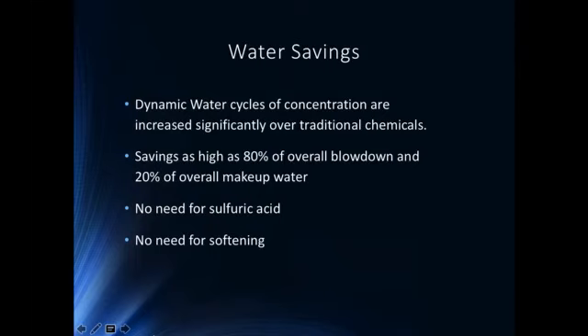So again, briefly talking about water savings, we're able to run much higher cycles of concentration than traditional chemical water treatment. In the Southern California area, we're typically running 10 to 12 cycles of concentration, where most are running 3, 4, 5, depending on the time of year. That savings can be as high as 80% of the overall blowdown and as much as 20% of the overall makeup. And those numbers can vary depending on the quality of the water in your area. And again, we're able to do this without sulfuric acid, without any kind of softening.